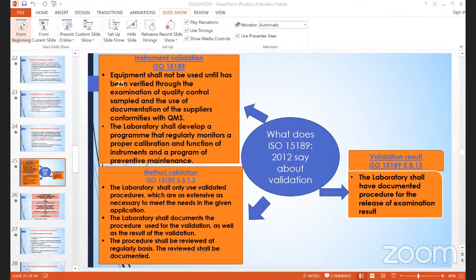So what does this standard say? According to it, for the instrument validation, equipment shall not be used until it has been verified through examination of quality control samples and the use of documentation of the suppliers in conformity with the QMS. So what does it mean? Thou shalt not use equipment until you have validated it. So if you are using equipment without validation, that is quackery. The laboratory shall develop a program that regularly monitors proper calibration and function of the instrument, and a program for preventive maintenance.